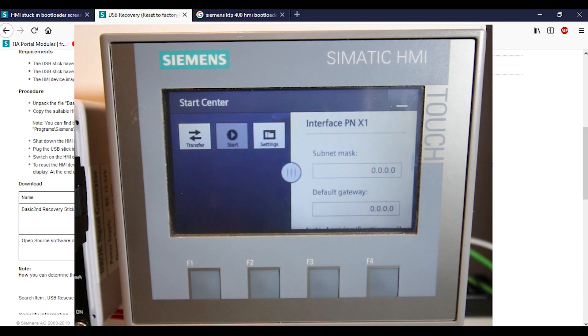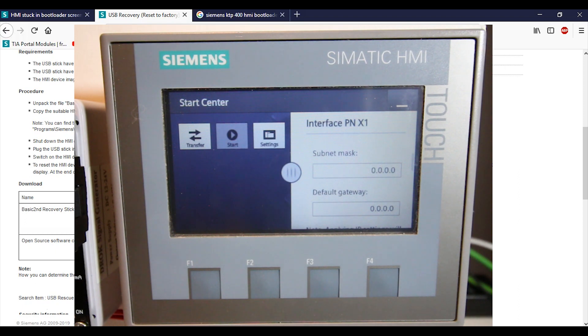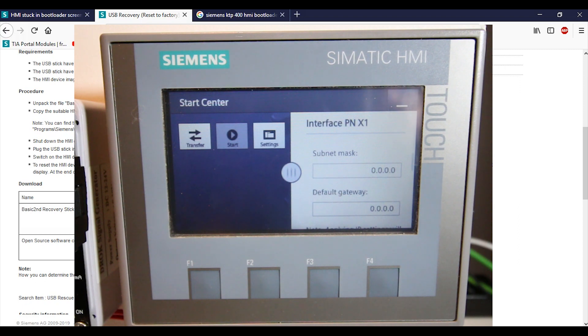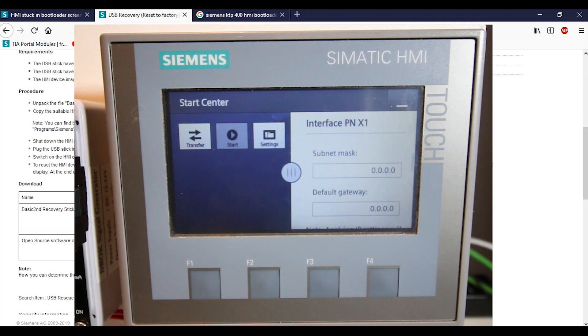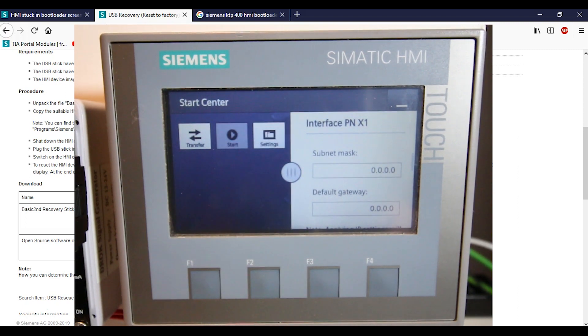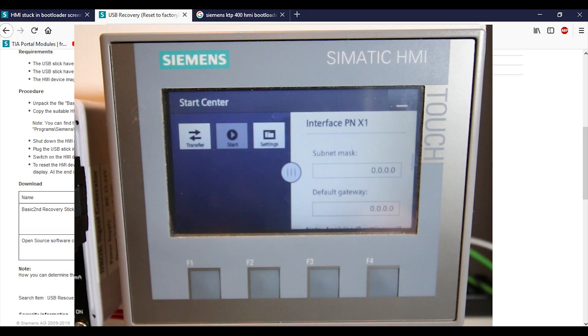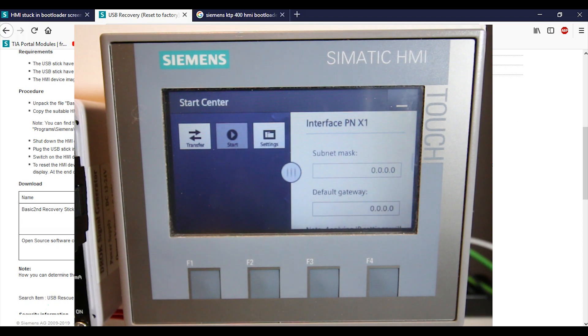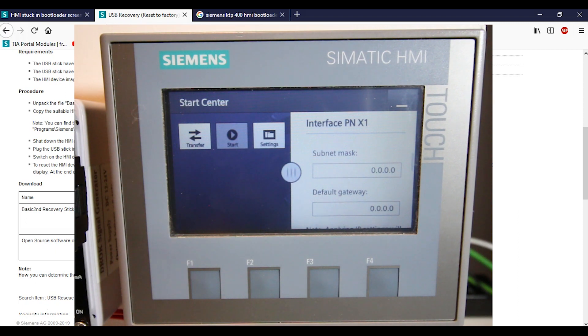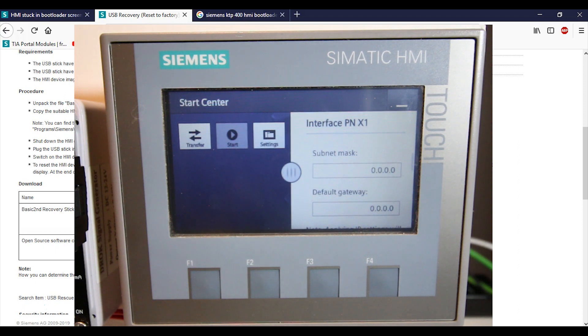Now if you have yourself or a customer that has this issue, you might want to do this once you've finished off a project and you're walking away from the customer. Just download that image onto a stick for them, onto a USB stick. If that HMI ever dies, you have the image, so you just leave it with them and they'll leave it in the office. If that particular KTP400 or 700 goes down, then you have the exact image that you've left with the customer, and you can walk them through the procedure on the phone. Then they can get it up and running, and then TIA Portal can talk to it. Alright guys, hopefully that helped you. It definitely helped me. Shout out again to the forum - all the answers are there, you just got to be able to take some time to find them. Thanks for your patience, we'll see you on the next one.